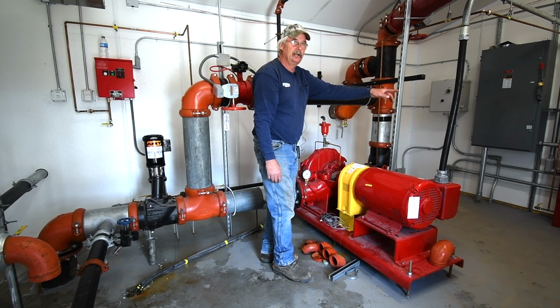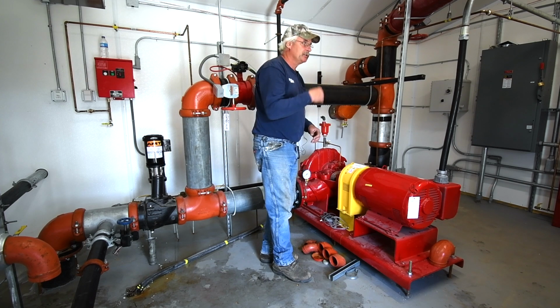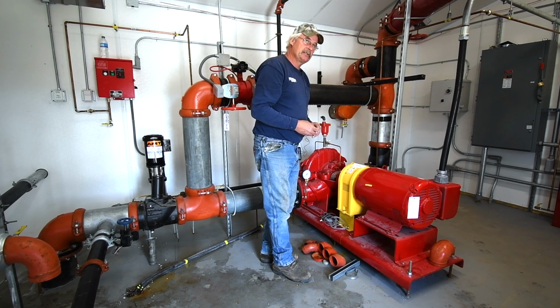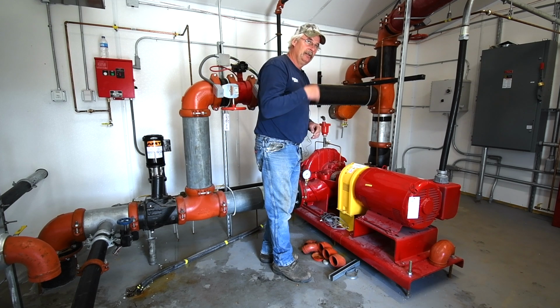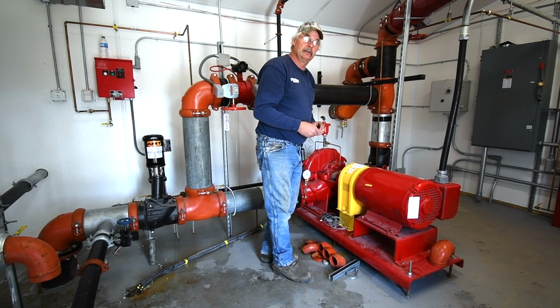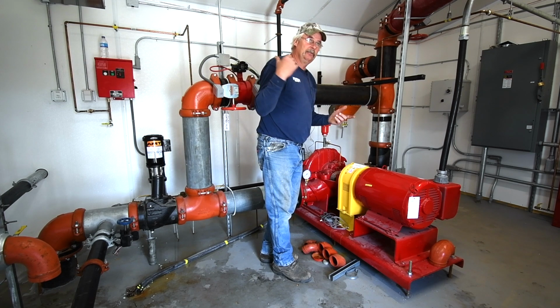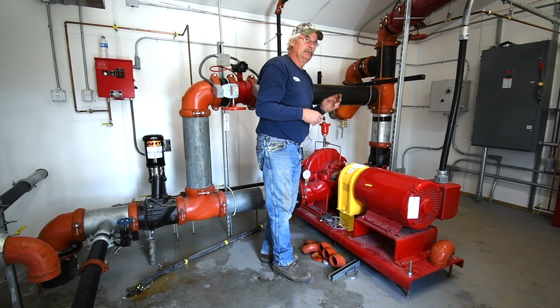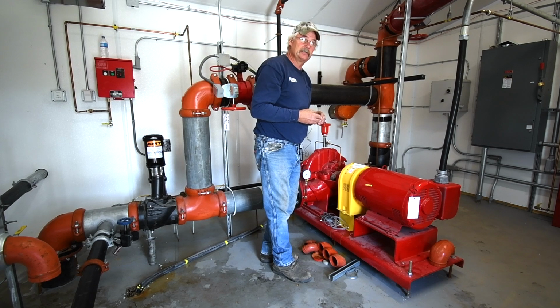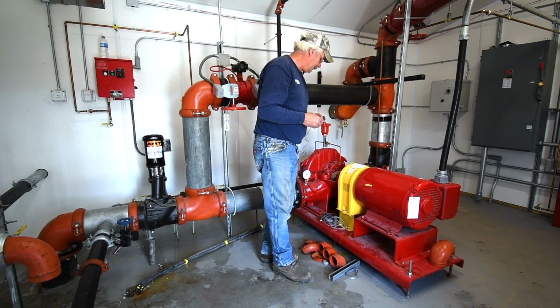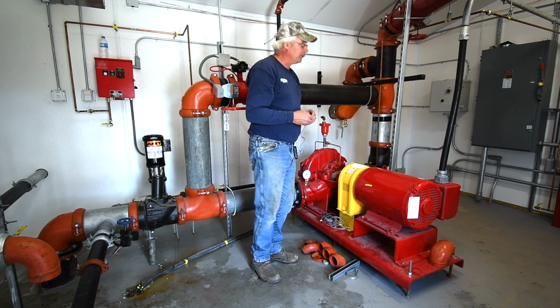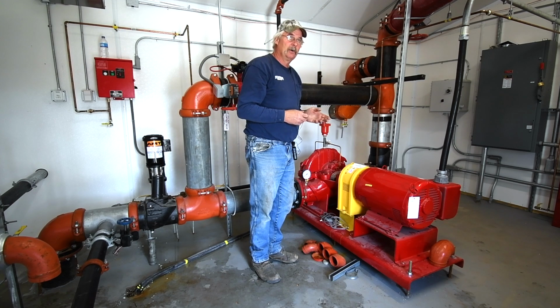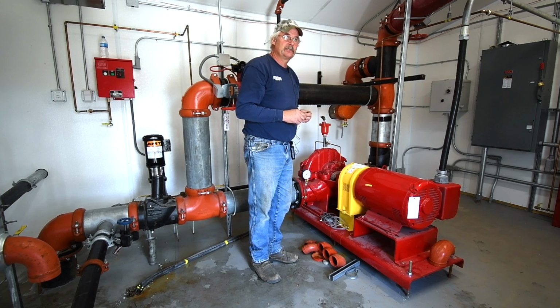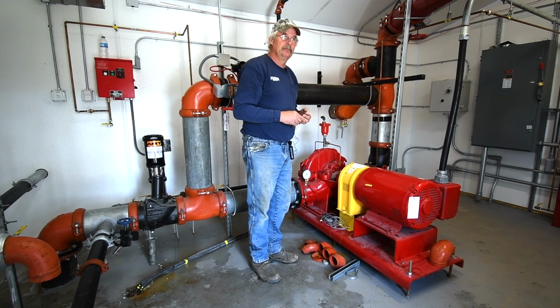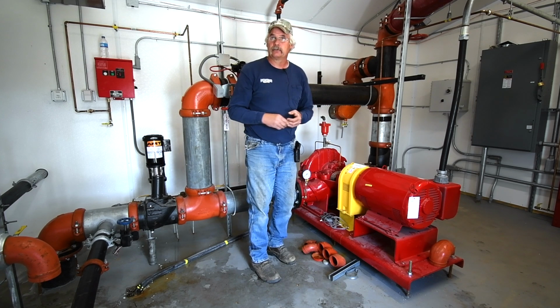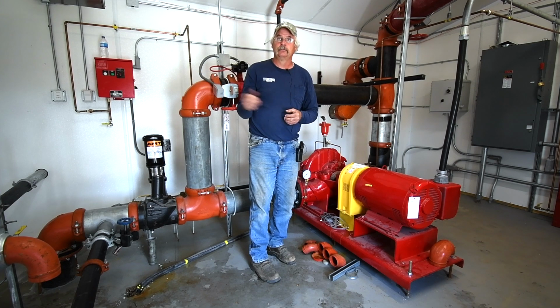We'll be doing start stops on the controllers. We'll be making sure that the diesel generator kicks in. We'll be shutting the AC power off, kicking the diesel generator on. We'll be checking the level of the water in the tank. We'll be checking the fuel and stuff in the diesel to make sure that's maintained and full at all times. And again, we'll be looking for start stops, power loss, phase reversal, temperature probe, horn and lights, and jockey pump.